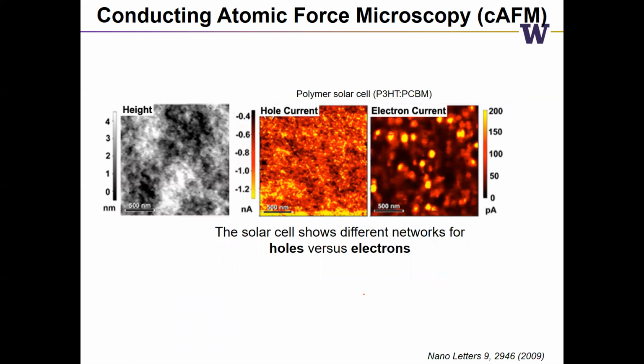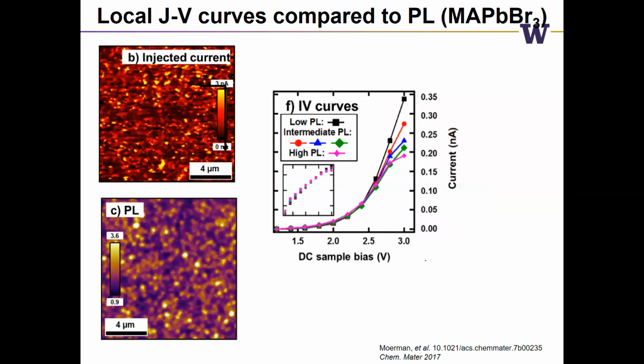What you can do with conducting AFM, well, you can measure all sorts of cool stuff. In this particular case, this is one of these old OPV samples, the P3HT:PCBM. You can see at one polarity, you measure the hole current, and it's fairly uniform over the system. Whereas if you switch to electron current, you see all these isolated hotspots of connectivity, presumably through PCBM networks. So you do see very different hole versus electron networks. In things like OPVs, where you have these two different components that control your conductivity, you see this pretty readily.